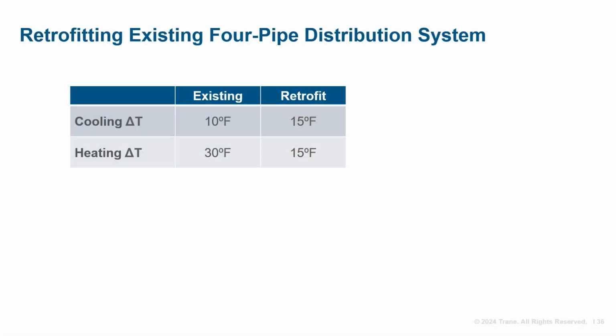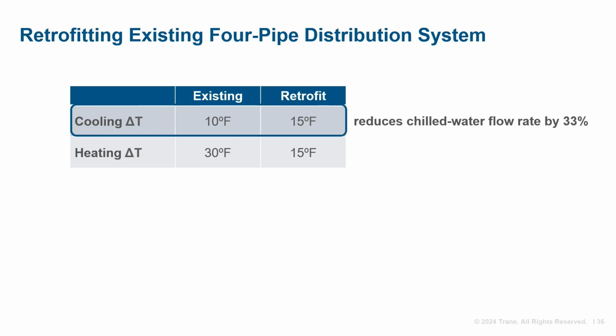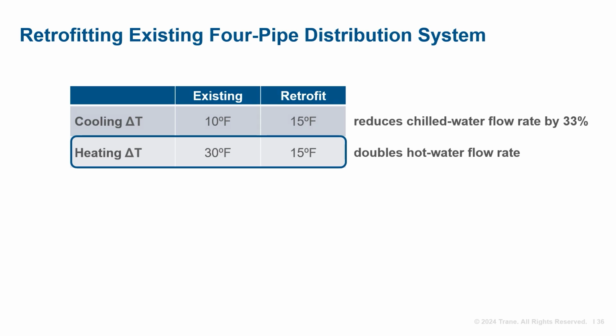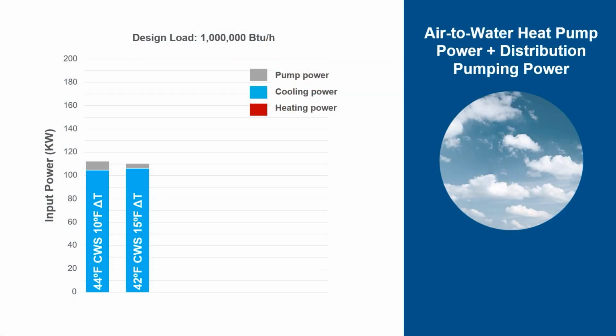Let's pause here and talk about pumping energy use. Recall the existing system was sized for 10-degree delta T in cooling. The 15-degree delta T in the new design will reduce chilled water flow by 33% and reduce cooling pump energy further by reusing what is now oversized branch and zone piping. However, the new design has a 15-degree delta T in heating, which doubles the zone hot water flow rate. In the big picture, the increase in distribution pumping power for heating is small compared to the heat pump power savings due to using 105-degree hot water, although the same is not true for cooling. To demonstrate this, this bar graph represents cooling design day with 1 million BTU per hour of cooling load. Changing from a 10-degree delta T to 15 degrees saves significant pumping power.